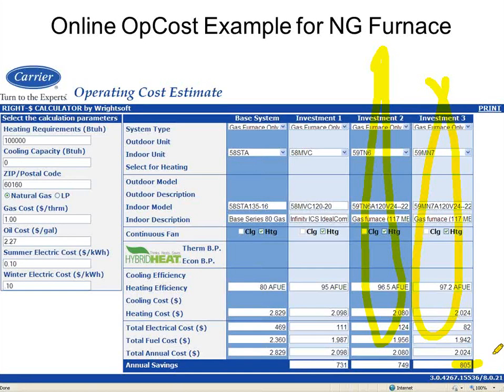Joe asks if the furnace maintains a fairly constant discharge temperature during the entire range of output, or is it cooler during the ranges of lower fire? The discharge temperature is not always going to be exactly the same, but it's not going to be too cool. We have algorithms in the system that control the blower speed as well as the gas flow. So if we were to keep the blower speed constant and we started lowering the gas flow, obviously our discharge air temperature would drop, and that's fine when I'm going from 120 down to 115, 110, etc. But I don't want it to get too cold, because if it's too cold, people perceive it as being cool.